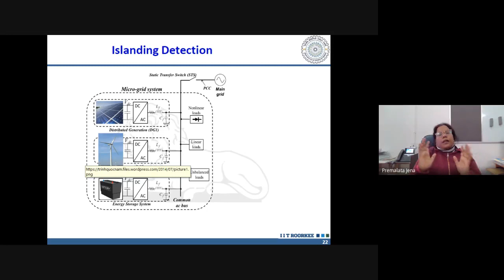The problem is that when this is disconnected from the main grid, my generation and load demand mismatch. Let's say the loads are 100% and the renewable sources are supplying 20-30%, and the main grid supplies the rest, maybe 70-80%. Now the main grid is off, so we only have 20% availability of power from renewables, but 100% load. That means there is an active power mismatch and reactive power mismatch between generation and loads.